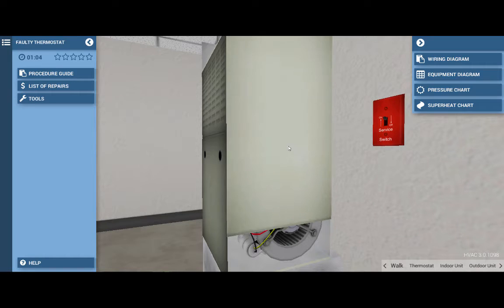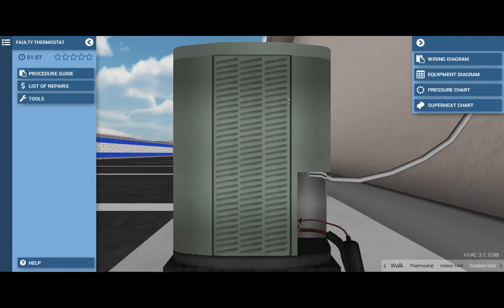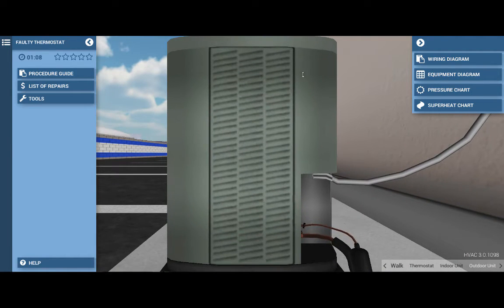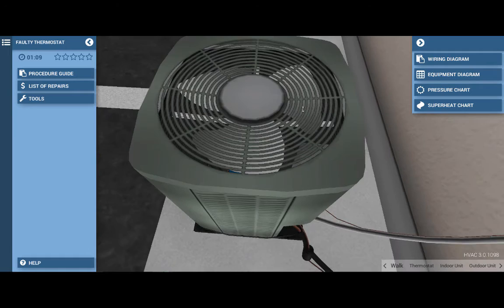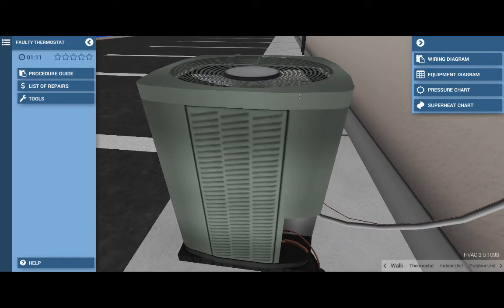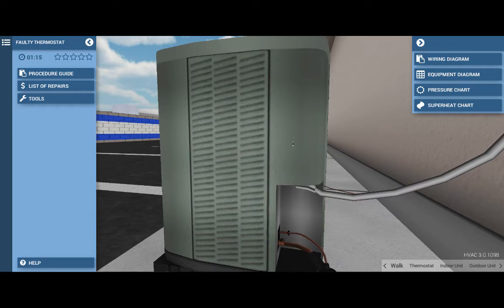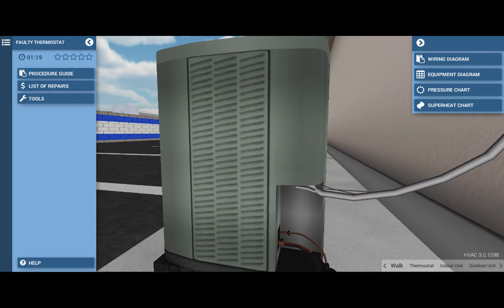Our next step is to go to the outdoor unit and see what's running out there. And when we proceed out there, we see that the condenser fan motor is not running, nor is the compressor running. So we have a problem that's affecting all three electrical loads.